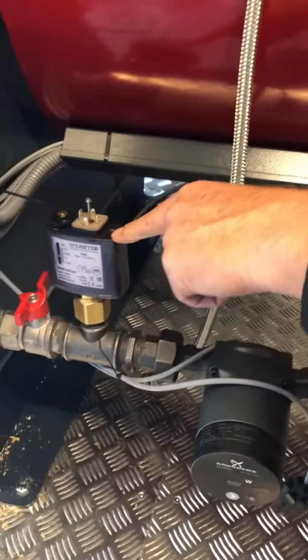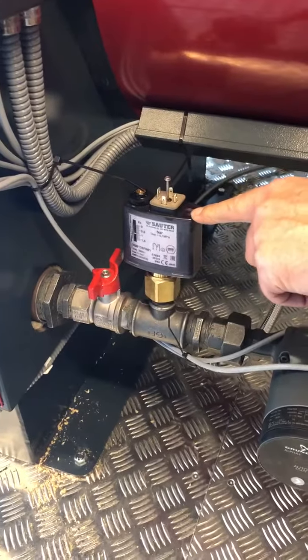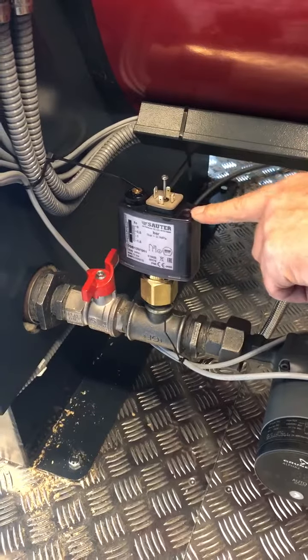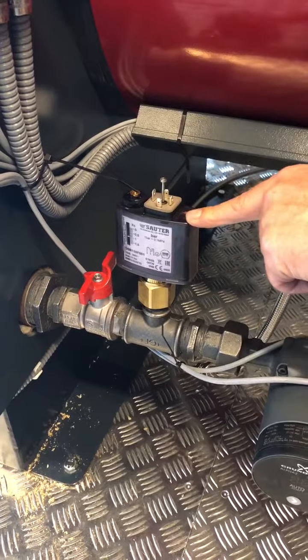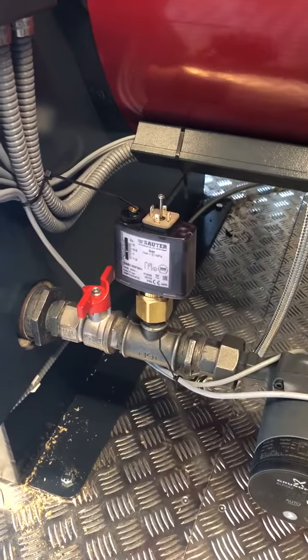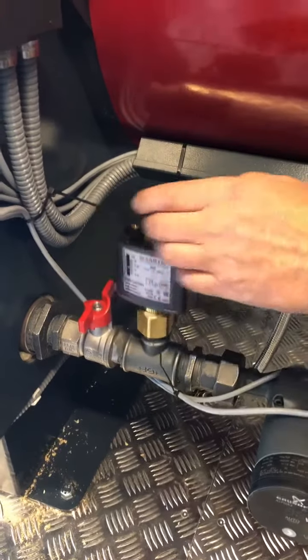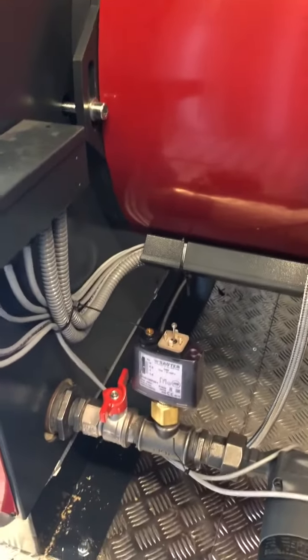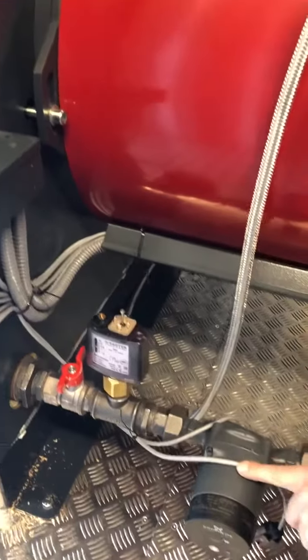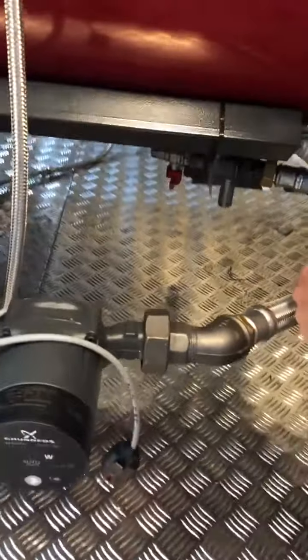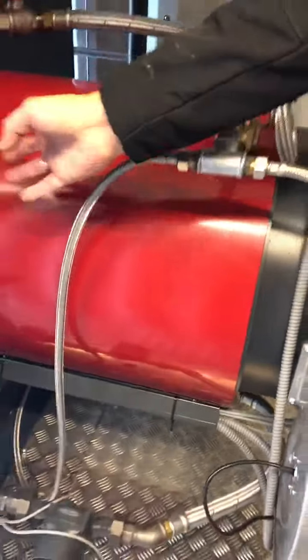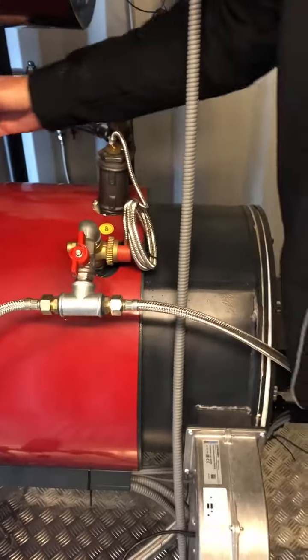This is the water pressure sensor, so if the water pressure in the system is too low, it shuts off. But with some of the container units where we've got an open expansion tank, this one is not here, we've got a water level sensor in the expansion tank. This pump here circulates the water up to the bottom of the burner tube, and the water circulates inside the burner tube, comes back to the top, and into the boiler again.